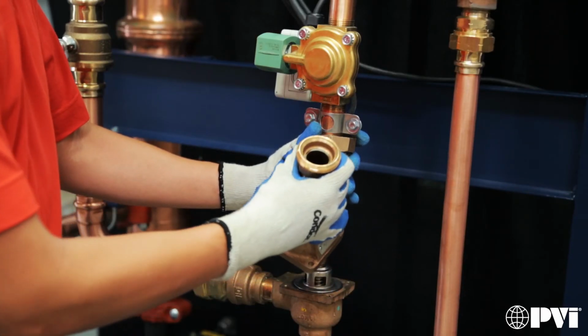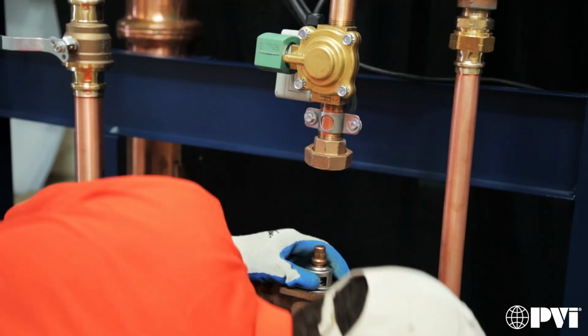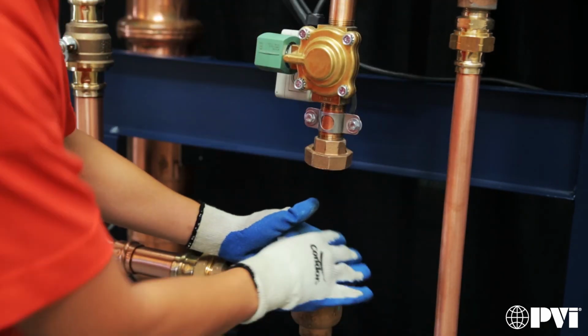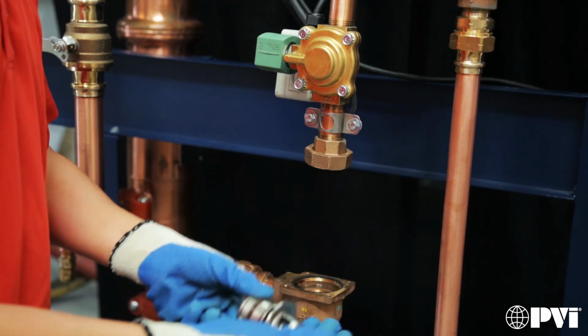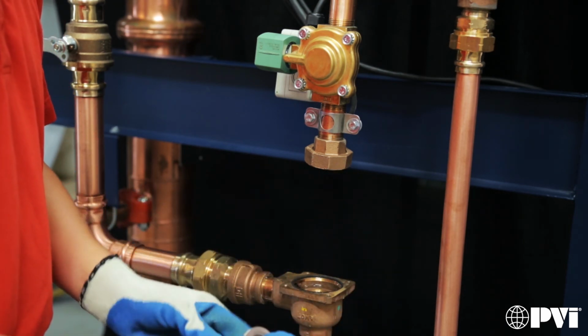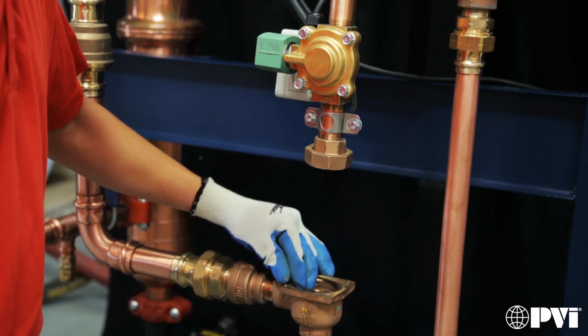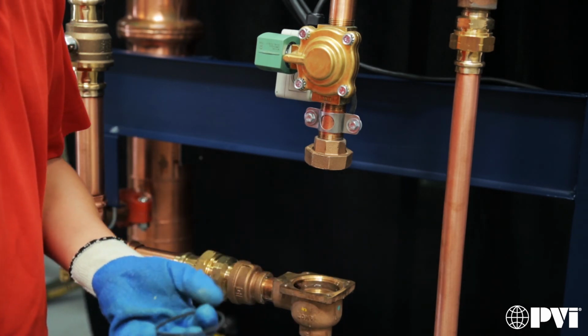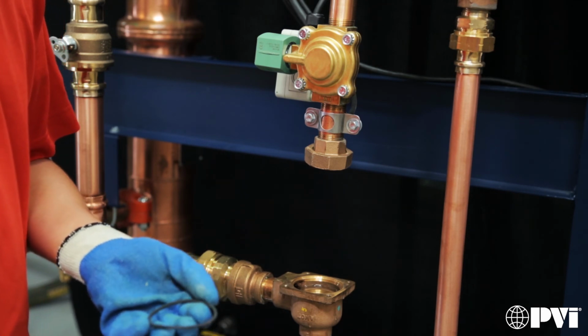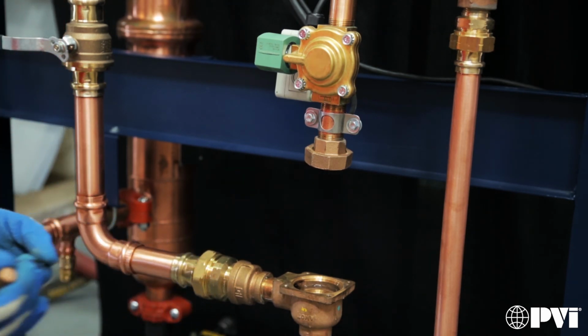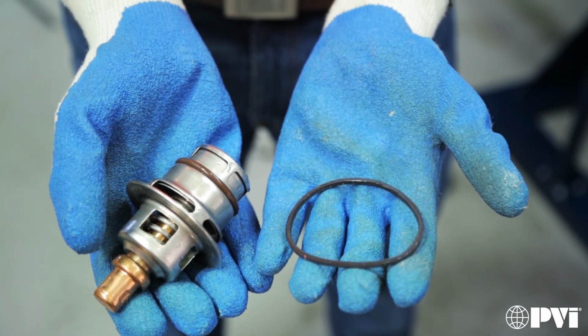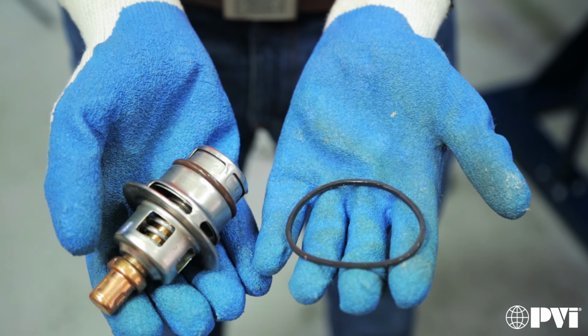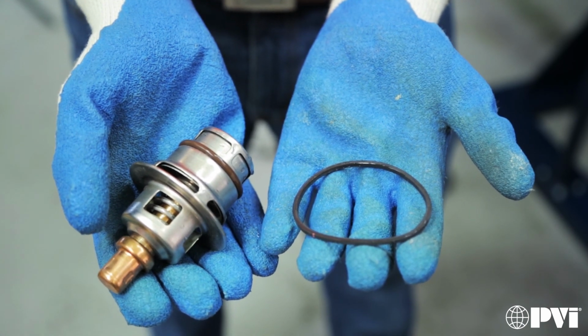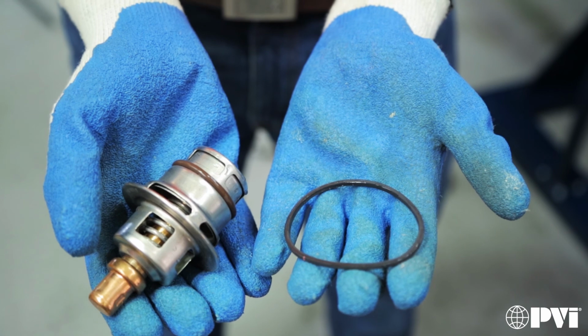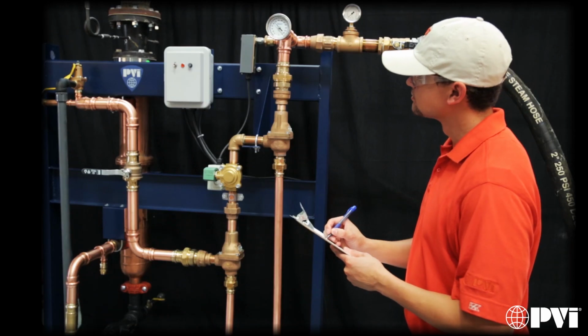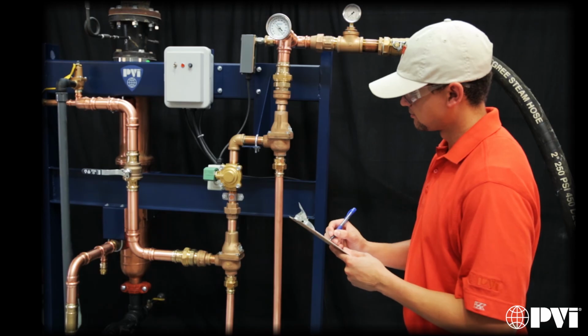If you experience a loss of temperature, you may inspect the temperature control valve for scale buildup. Remove the 4 bolts from the valve bodies and loosen the pipe union above the valve to free the halves of the housing and separate. Inspect the element. If necessary, descale these hot water surfaces in the cleaning solution. Return the element and 2 new O-rings to the valve body and reinstall. Tighten all fittings. O-ring seals should be replaced whenever replacing elements. When reinstalling seals or installing new ones, always lubricate them with light food-grade grease to make installation of the element easier. You may now follow the startup procedure to return the water heater to service.